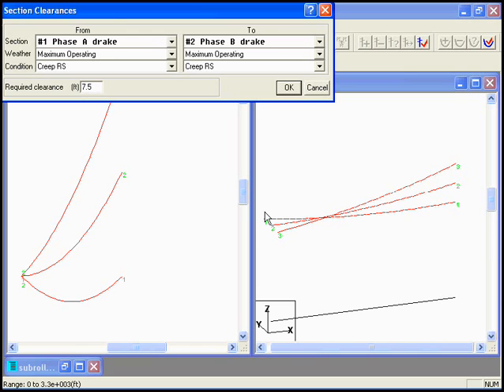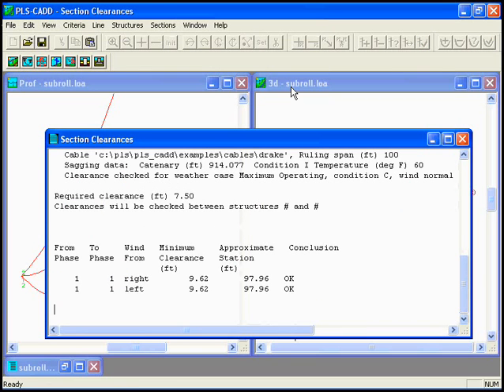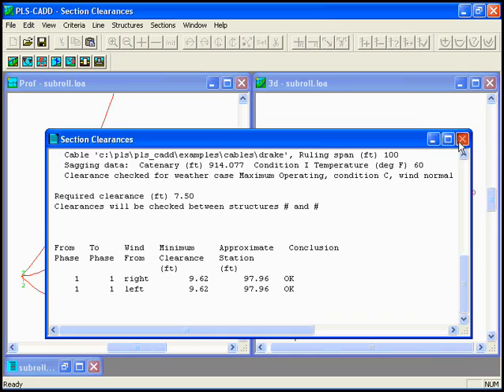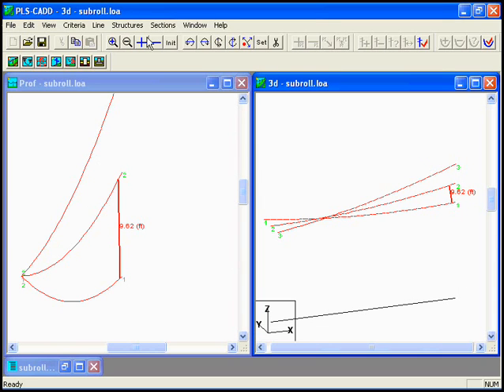If you remember, at substation, we have 10-foot phase spacing, and at the vertical transmission pole, we have 10-foot phase spacing. So we'll click OK. We have 9.62 feet of clearance at approximately station 97.96 of our 100-foot span. Everything's fine, so we don't have any clearance violations. And that's great. Let's do one more example here.